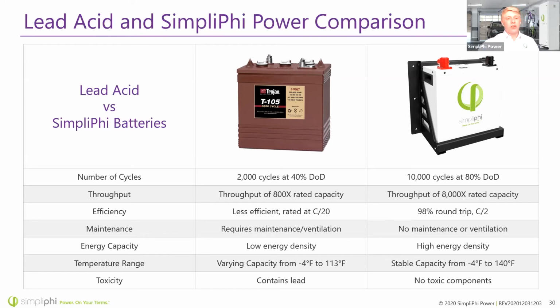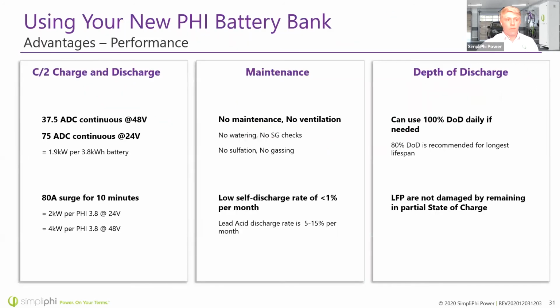Also, health and safety benefits: no toxic components with Phi batteries, meaning there's no lead, no heavy metals. Performance advantages: a higher charge and discharge rate of C/2, and a big surge of 80 amps for 10 minutes. That goes for both our 48 volt and 24 volt batteries. The 24 and 48 volt 3.8 kilowatt hour batteries specifically is what that 80 amp surge rating is for. Not only is there going to be no maintenance, but no concern as far as self-discharge. The self-discharge rate is so minimal, it's less than 1% per month, compared to lead acid's 5 to 15.